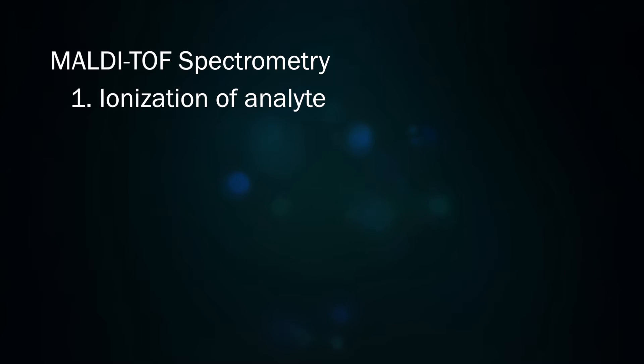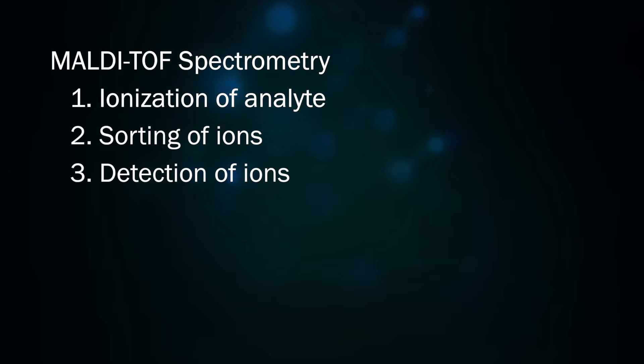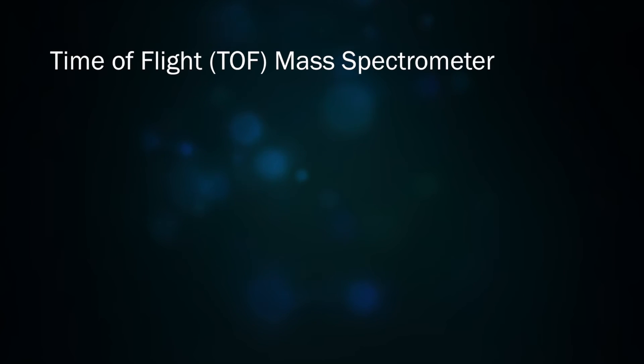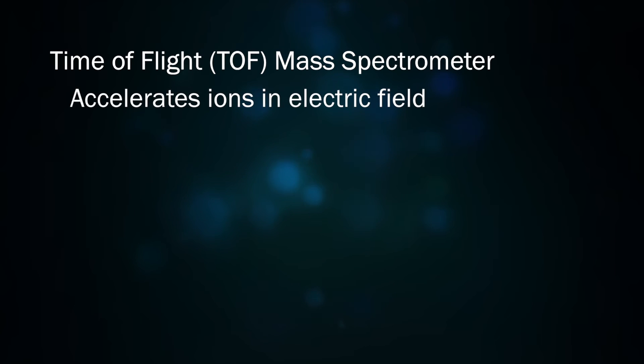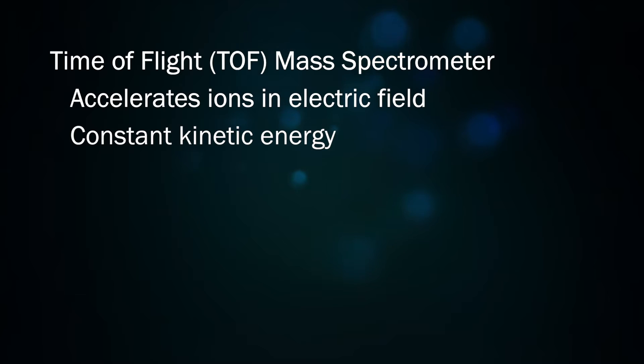Now that the gas phase analyte ions have been generated, their masses can be analyzed by the time-of-flight mass spectrometer. The time-of-flight process accelerates the gas phase ions in a high-voltage electric field. This field imparts a constant amount of kinetic energy on the ions. Because kinetic energy is equal to one-half mass velocity squared, a constant kinetic energy will cause the smallest of the ions to travel the fastest.